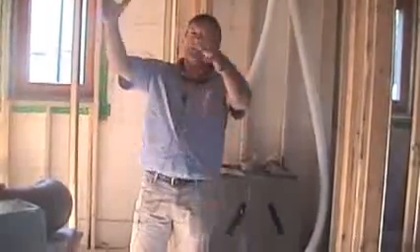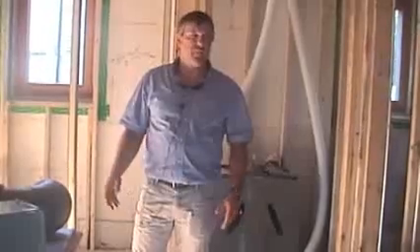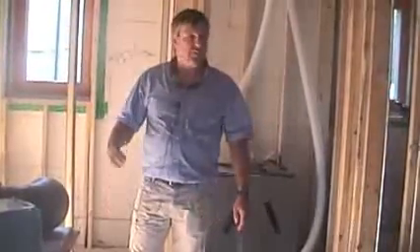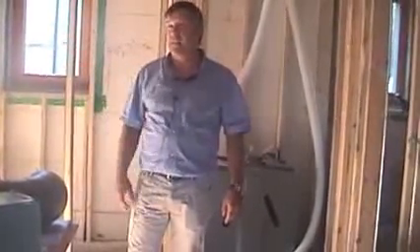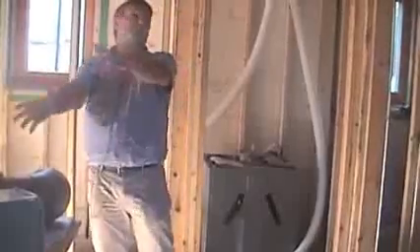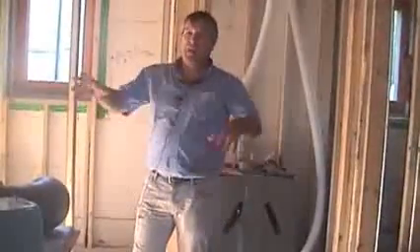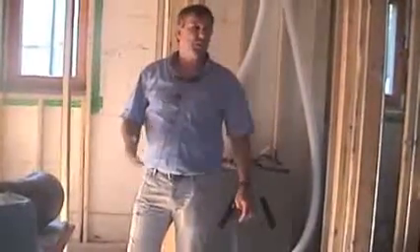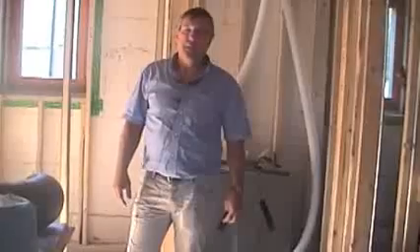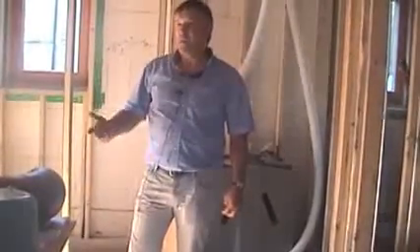Yes. We had a project in California where we went out and looked at it. They ordered like 5 extra rolls of ducting, and we're like, what, that can't be right. And we went out and looked at it, and he had run them all the way from a crawl space all the way up. There was a bundle this big going all the way to the upstairs. We had them run 2 trunk lines and took away 400 feet of duct. So we reduced it by that.